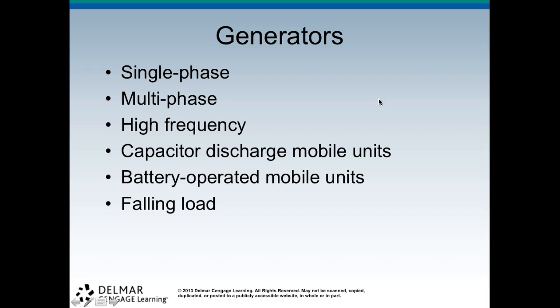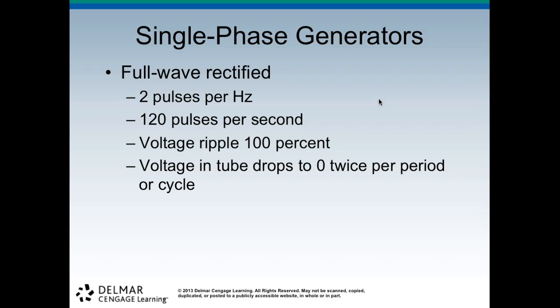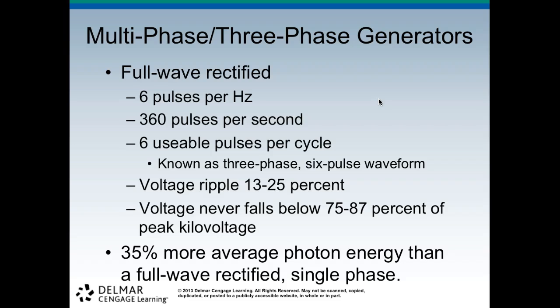Okay, generators. So let's talk about those. There's single-phase, multi-phase, high-frequency, capacitor discharge mobile units, battery-operated mobile units, and falling load. So single-phase generators, it's full-wave rectified. We have 2 pulses per hertz. There's 120 pulses per second, so the voltage ripple is 100%. The voltage in the tube drops to 0 twice per period or cycle.